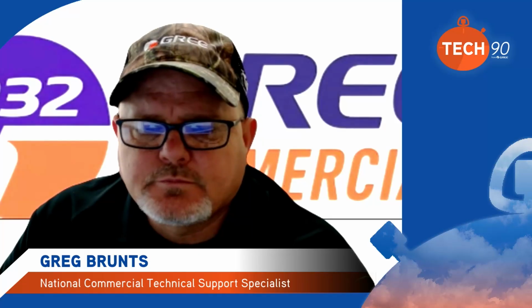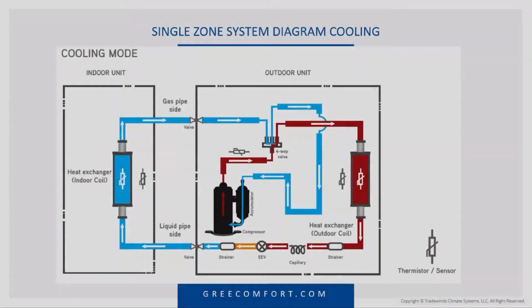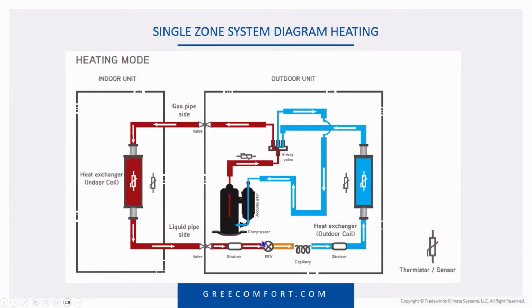On this screen, you will see that I've got a mini split piping diagram. The reason why I brought this up from yesterday is mainly to point out that in a mini split system, your EEV or capillary, you can use an EEV and a capillary, or just an EEV, or just a capillary. But as you see here, your metering device is in the outdoor unit. That's the main point here.